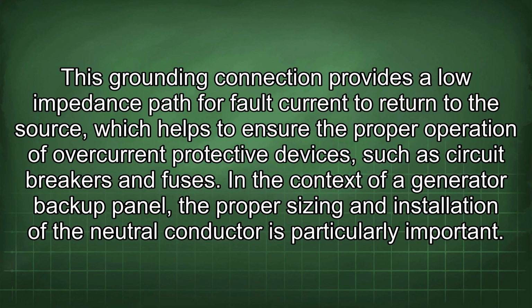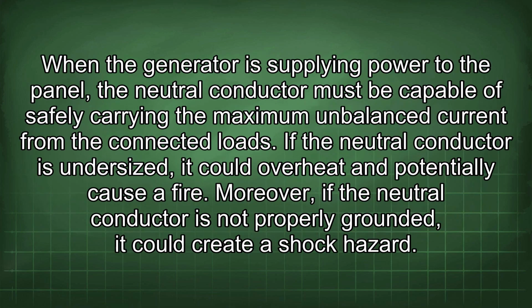In the context of a generator backup panel, the proper sizing and installation of the neutral conductor is particularly important. When the generator is supplying power to the panel, the neutral conductor must be capable of safely carrying the maximum unbalanced current from the connected loads. If the neutral conductor is undersized, it could overheat and potentially cause a fire. Moreover, if the neutral conductor is not properly grounded, it could create a shock hazard.